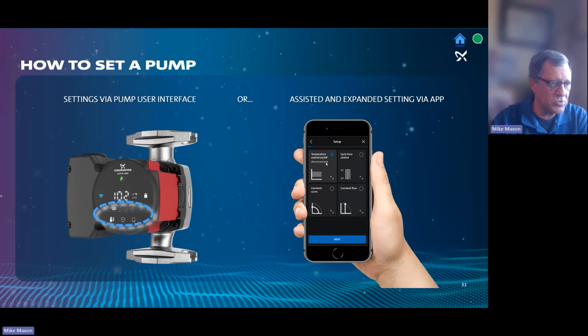Do you want to set it on temperature control, or just put it on a cycle, on so many minutes, off for so many minutes, or run a constant curve or constant flow? And once you do this screen, then you can go through and set those temperatures, set the flow rates. You could set the fallbacks. Fallbacks are minimum time on, minimum time off, maximum time on, maximum time off. So you can set those numbers.